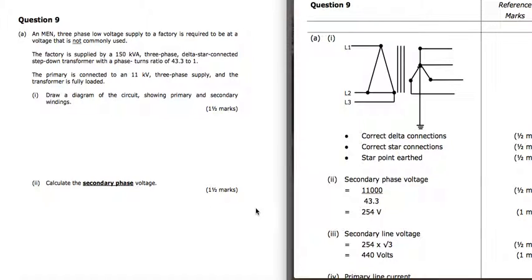Calculate the secondary phase voltage. So the primary phase voltage is 11 kV. We've got 11 kV across there. Because it's delta, the primary phase and line voltage is going to be exactly the same. So it's going to be 11 kV on that phase. And so on this phase here is going to be 43.3 times less than over here. So we've got 11 kV divided by 43.3, which is our turns ratio, gives me 254 volts. Now that 254 volts is the phase voltage.